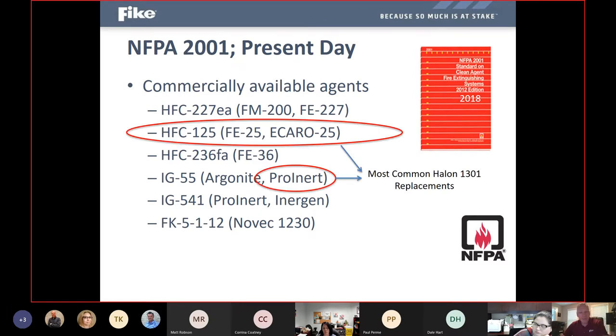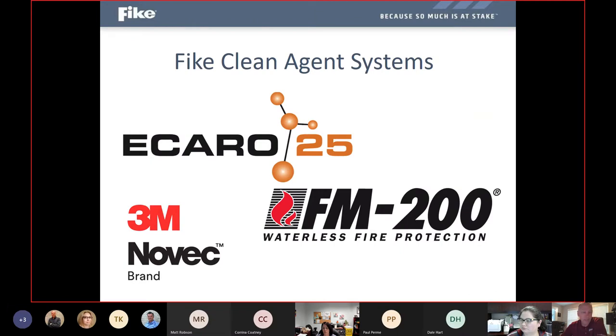Your most popular Halon 1301 replacements are Ecaro 25 and ProInert, primarily because they are the ones most likely to be able to utilize some, if not all, of the existing piping from a Halon 1301 system. The other agents on the screen will not be able to. You have to remove the tank, the piping, the nozzles, everything from Halon 1301 and redesign new. But those two that are circled may in fact be able to utilize most of the existing piping around the system, so you can save on some installation fees and make it practical to convert a system over. The Fike clean agent systems that are the most popular are the Ecaro 25, FM200, and 3M Novec 1230.